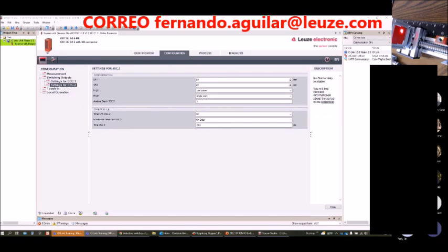And so how we looked at it is we took an IO-Link version of that sensor, or IO-Link capable version. We used this software to set it up and configure it. They configured not only the distances for the switching points, they configured the normally open, normally closed for each switching point, which they had to configure very specifically for their IO.